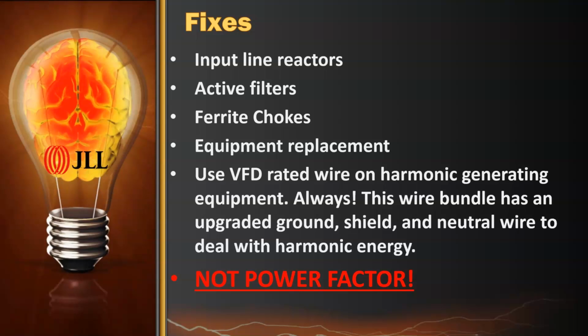That's pretty expensive. Okay. Does lowering the harmonics lead to a lower billed demand? Yeah, power meters, when they measure demand and power factor particularly, they're just looking at phase angle, and so they don't even care about kVA demand and consumption these days. Like in the last probably 15 years, they stopped doing that. They just look at phase angle, and they do some stuff there. For kVA demand, it's a different kind of calculation in the meter that's not really affected by harmonics. It's just not. So just to take like a minute to explain this.